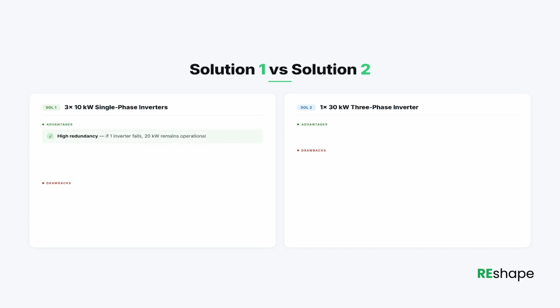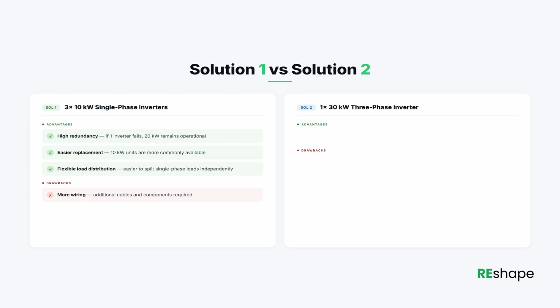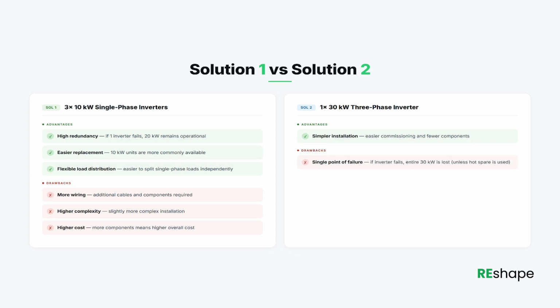To compare these two solutions, I should say the first solution has higher reliability and redundancy, and if one inverter fails, 20 kW will remain. Easier replacement, as usually 10 kW is more common, and easier to distribute single-phase loads. However, it needs more wiring and components, slightly higher installation complexity, and the cost will be higher. On the other hand, the second solution will have simpler installation and commissioning. However, if the inverter fails, the whole 30 kW will be lost.